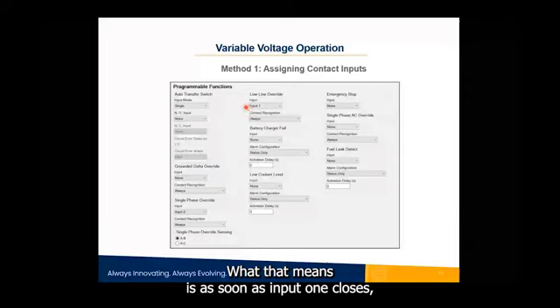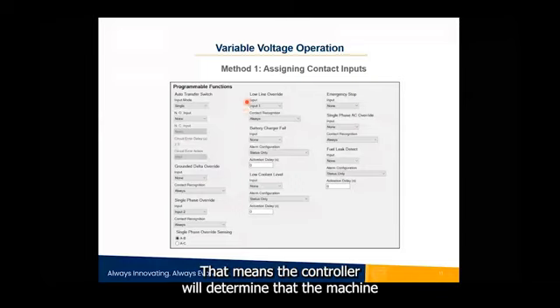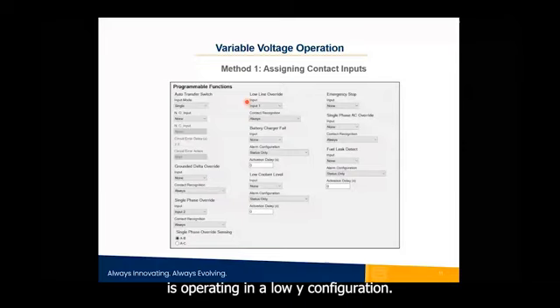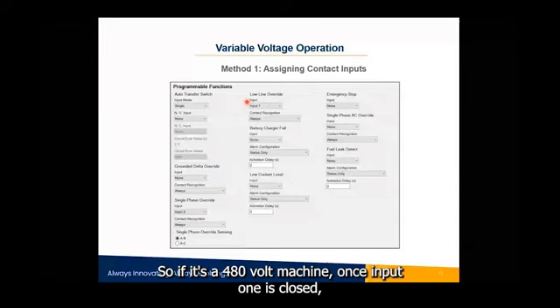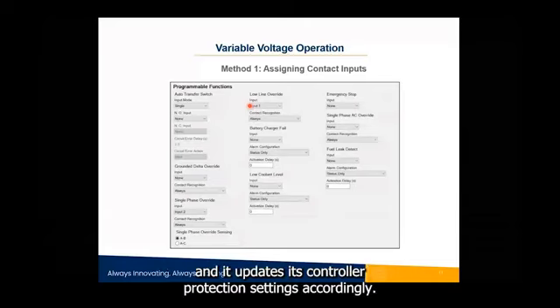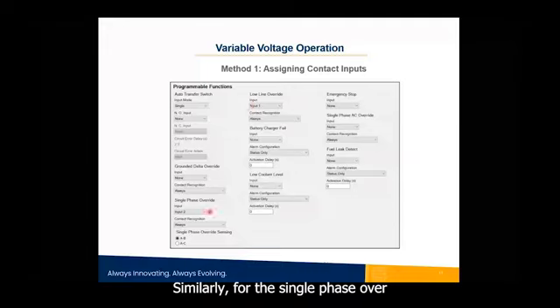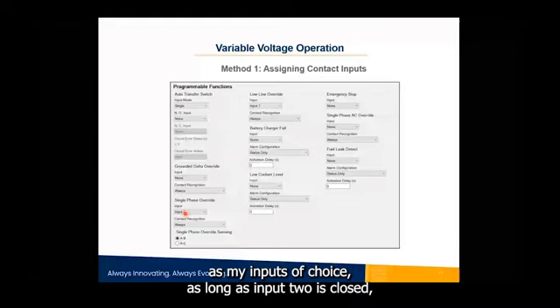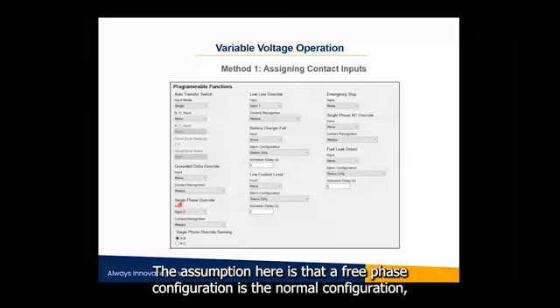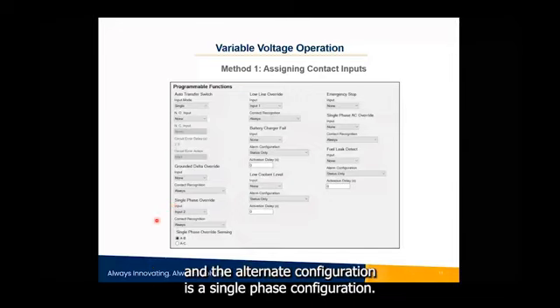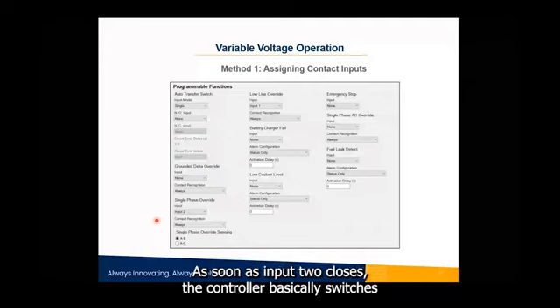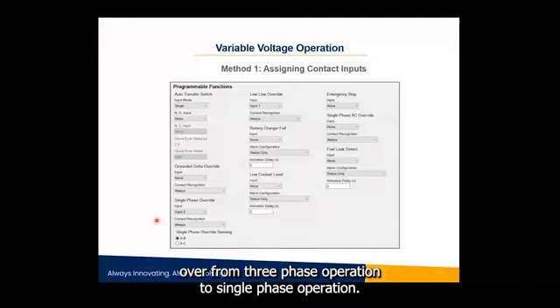What that means is as soon as input one closes, then the controller will be given a low line override status. That means the controller will determine that the machine is operating in a low Y configuration. So if it's a 480 volt machine, once input one is closed, the controller now sees the machine as a 240 volt machine, and it updates its control and protection settings accordingly. Similarly, for the single phase override, input two as my input of choice. As long as input two is closed, then the controller is given a single phase override status. The assumption here is that a three phase configuration is the normal configuration, and the alternate configuration is a single phase configuration. As soon as input two closes, the controller basically switches over from three-phase operation to single phase operation.